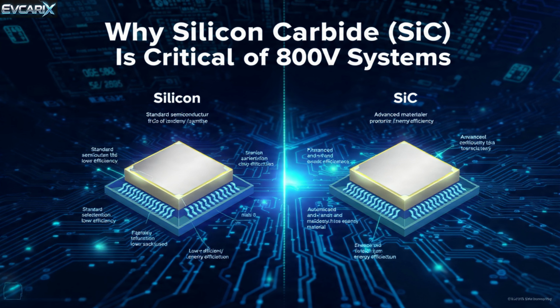Increasing voltage also has a limit. This limit is well explained by Paschen's law. Depending on pressure and distance, air can break down at a certain voltage and create an arc, a spark. According to standards, the low voltage limit on the DC side is actually 1500 volts. That means 1000 volts is still considered low voltage, but in practice, going above 1000 volts increases the risk of arc formation according to Paschen's law. It also raises component costs in a nonlinear way and moves away from the most efficient operating window of silicon carbide technology. That's why the automotive industry generally prefers the 800 to 900 volt range.